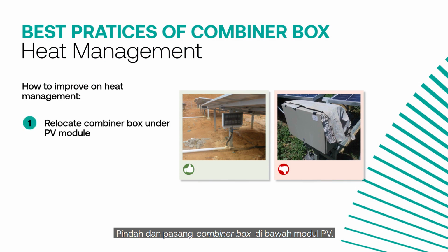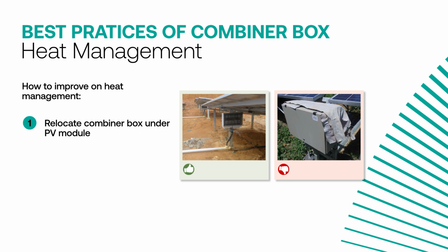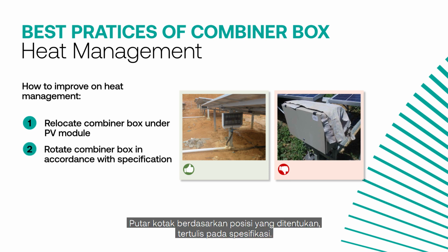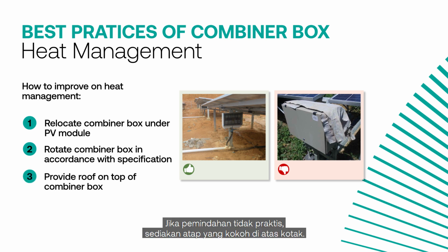Relocate and install the combiner boxes under the PV modules. Ensure that there is no direct sun exposure at any time of the day. Rotate the box in accordance with the predefined position that is written in the specification. If relocation is impractical, provide a robust or fixed roof on top of the box.